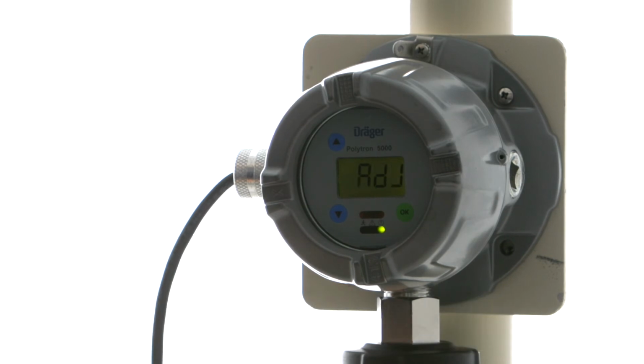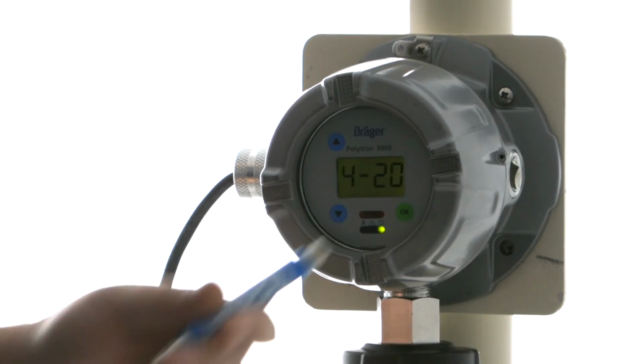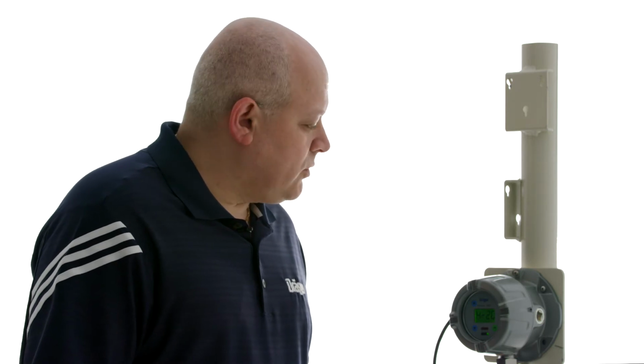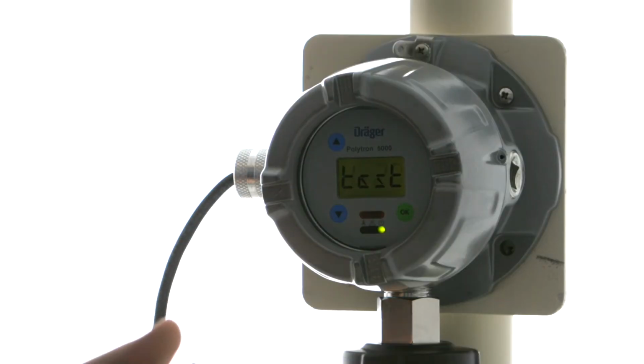Next is the span adjust, which is our span calibration. So the 4 to 20 milliamp test is used to commission the Polytron 5100 when it's connected to a controller. You're able to select a specific current that is output from the transmitter such that you make sure the controller sees the exact same value as the detector is outputting.